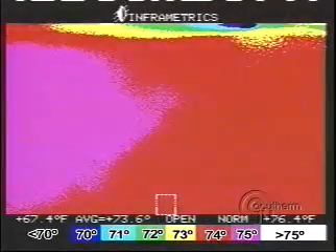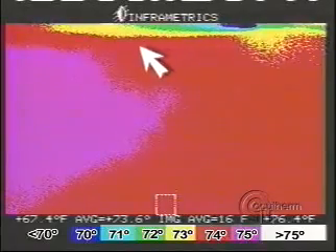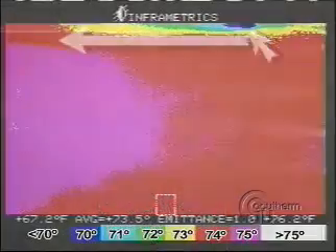Looking at an infrared image of a screen hung in the center of the 275 CFM primary air flow, we can see the air temperature associated with different parts of the same room. Notice how the colder supply air — shown as black, blue, green, and yellow — clings to the ceiling, while the overall room temperature, shown with red and magenta, is between 74 and 75 degrees Fahrenheit. Watch how quickly the black 55-degree supply air is warmed to room temperature — this is also due to the high discharge velocity of the Thermafuser module.